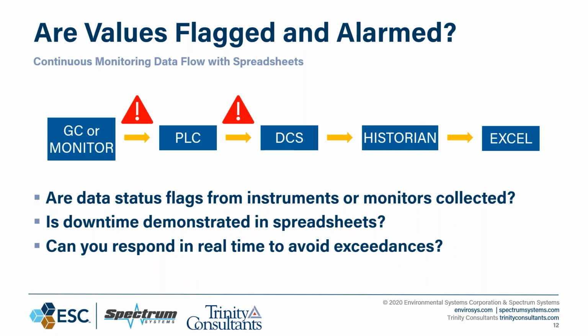Another expectation of your data acquisition handling system: are your tag values, your parameter values, being flagged and/or alarmed? This is important in a DAS. You want data status flags from your instruments, good or bad, you want all of them collected. This is a continuous monitoring system. You should be collecting data status flags continuously, whether the data is valid or invalid.